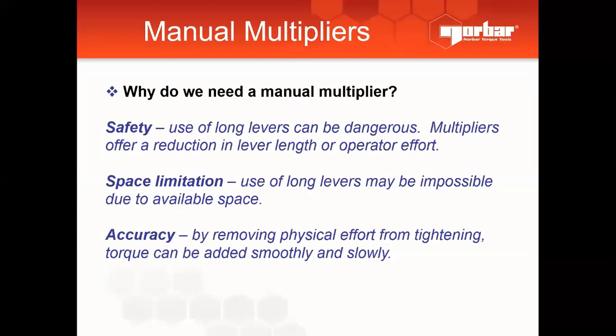Instead of using a long lever torque wrench to apply 1,000 and above Newton meter, you may use a multiplier to reduce the length and the operator effort. Second, it'll be the space limitation. Normally you use a long torque wrench, and sometimes you have space limitation because the torque wrench is 1 meter long. So when you use a manual multiplier, you may use a shorter torque wrench to apply on the job.